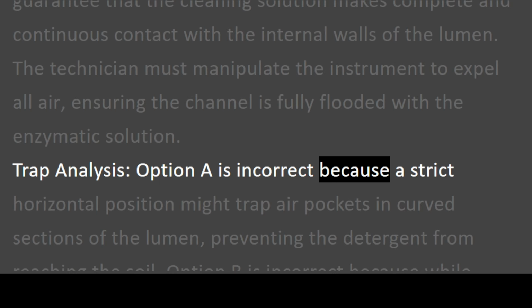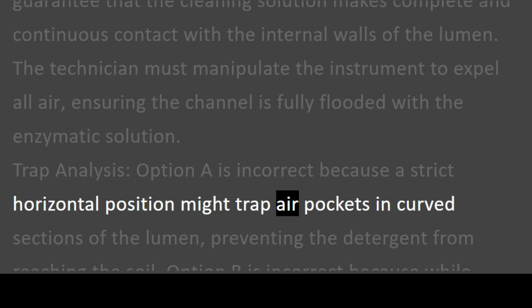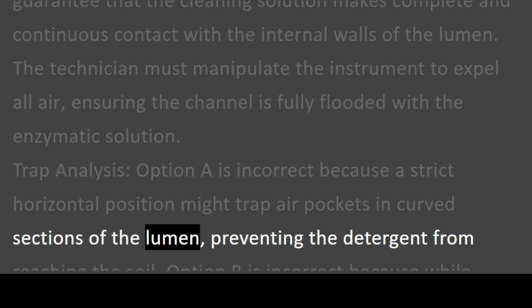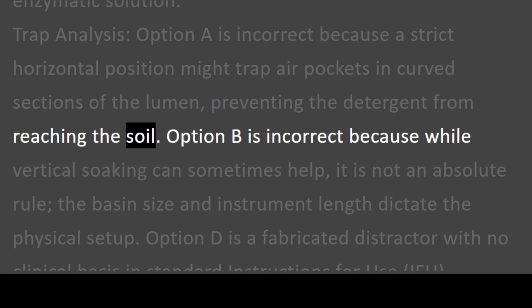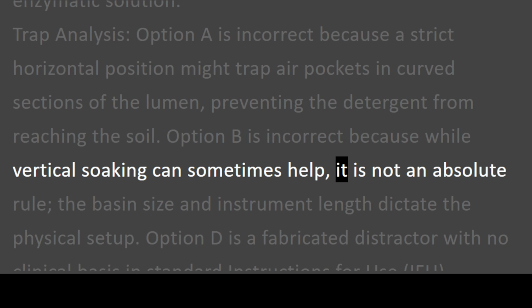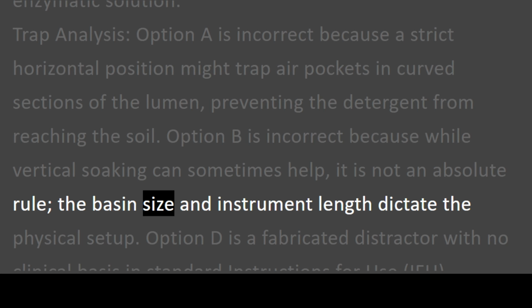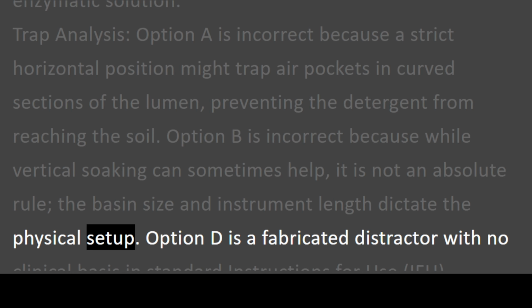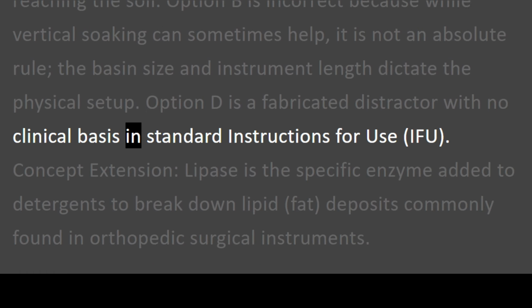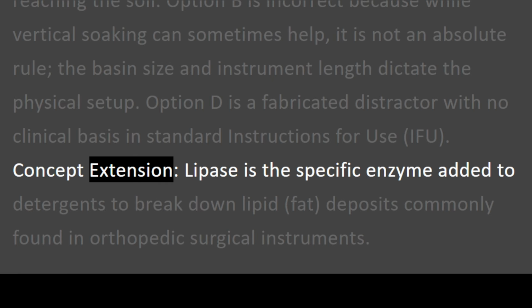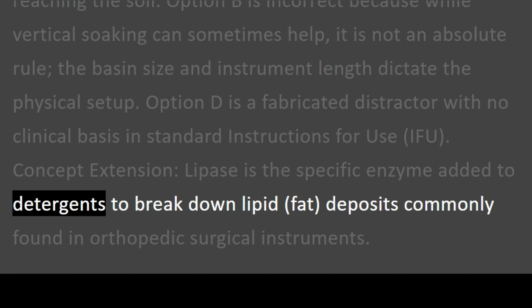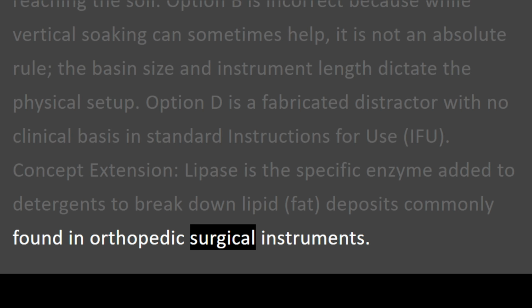Option A is incorrect because a strict horizontal position might trap air pockets in curved sections of the lumen, preventing the detergent from reaching the soil. Option B is incorrect because while vertical soaking can sometimes help, it is not an absolute rule. The basin size and instrument length dictate the physical setup. Option D is a fabricated distractor with no clinical basis in standard instructions for use, IFU. Concept extension. Lipase is the specific enzyme added to detergents to break down lipid fat deposits commonly found in orthopedic surgical instruments.